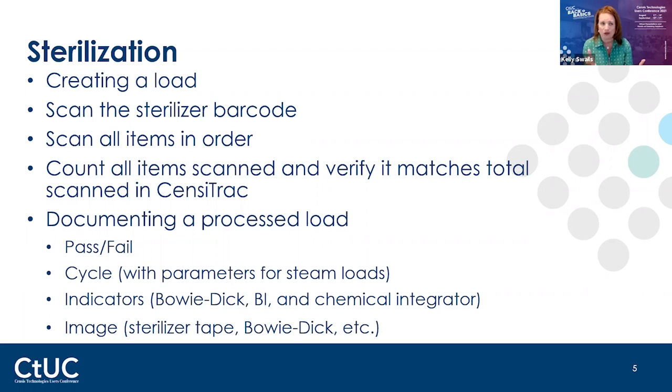I do see where you have your IUSS sterilizers for the OR. And maybe if you don't have a tablet or a PDA or some other portable device, or there's no computer up there, then you probably do need a sterilizer barcode down in SPD or SPS for those. But I look at it as a little different because chances are you're scanning all 3 of them for a Bowie Dick.